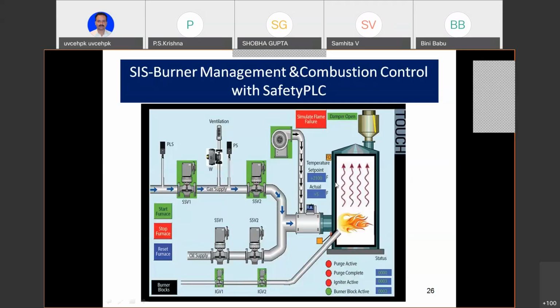Now, this is a very, very good example of a safety instrumented system, which is now controlled by a PLC. In the good old days, it used to be controlled by a relay circuit, now by a PLC. Now the PLC here is a safety PLC, a gold-plated PLC. Why is it gold-plated? We can talk for 1 hour on that PLC, but today is not the day for that. For example, you go for Tricon, triple modular redundancy, which has a voting system built in for everything.